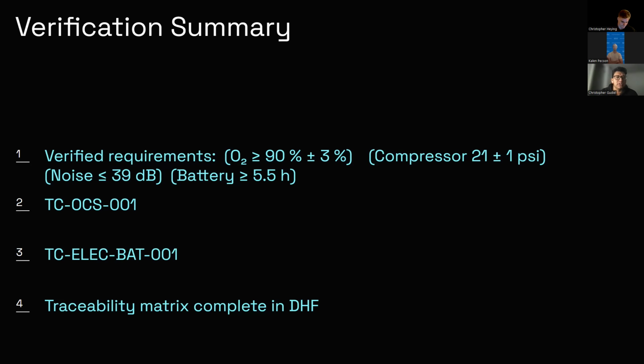So this is our verification summary. During our verification, we confirmed all essential performance requirements. Starting with the oxygen purity, we wanted greater than or equal to 90% with an uncertainty of plus or minus 3%. For our compressor pressure, it was 21 with an uncertainty of plus or minus 1 psi for 8 continuous hours. Our noise is less than or equal to 39 decibels, and our battery life is greater than or equal to 5.5 hours.